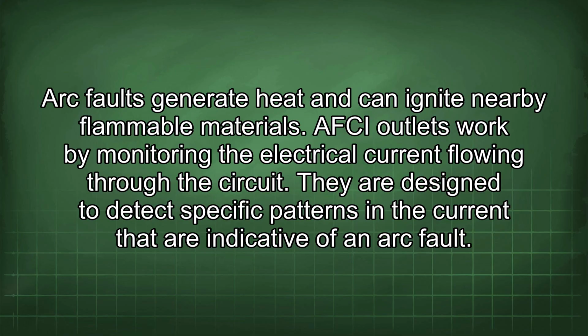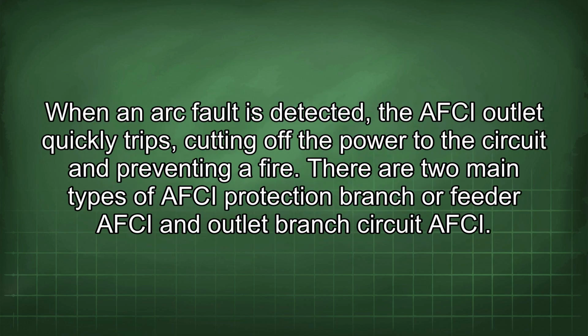AFCI outlets work by monitoring the electrical current flowing through the circuit. They are designed to detect specific patterns in the current that are indicative of an arc fault. When an arc fault is detected, the AFCI outlet quickly trips, cutting off the power to the circuit and preventing a fire. There are two main types of AFCI protection: branch or feeder AFCI and outlet branch circuit AFCI.